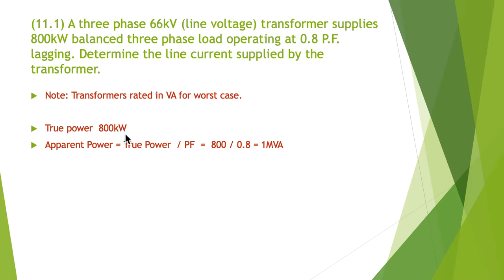We know that the true power is 800 kilowatts. One way to determine the apparent power is we know that true power divided by the power factor will give us the apparent power. So 800 kilowatts divided by 0.8 is going to give you one million or one MVA.